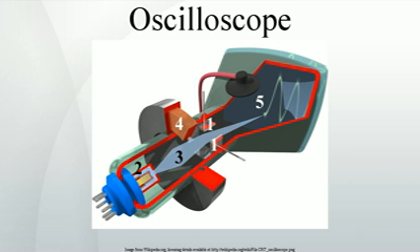Often the observed signal is offset by a steady component, and only the changes are of interest. A switch, AC position, connects a capacitor in series with the input that passes only the changes, provided that they are not too slow. Slow would mean visible. However, when the signal has a fixed offset of interest, or changes quite slowly, the input is connected directly, DC switch position. Most oscilloscopes offer the DC input option.